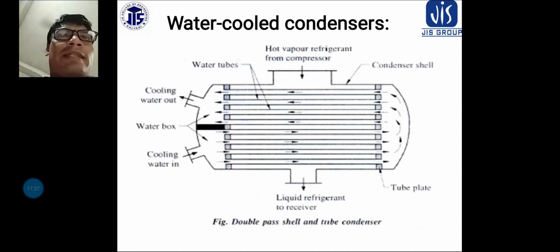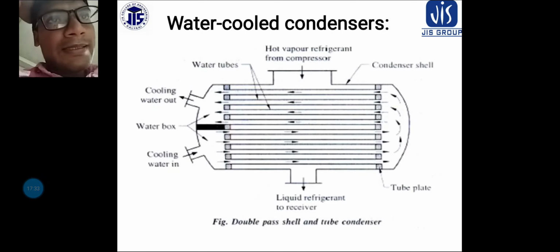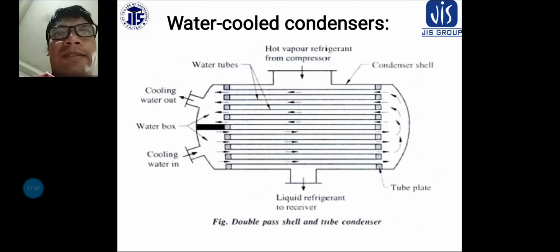The refrigerant is contained in the steel shell between the tube sheets. The water circulates in the annular space between the tube sheet and the end plates, the end plates being baffled to act as manifolds to guide water flow through the tubes.